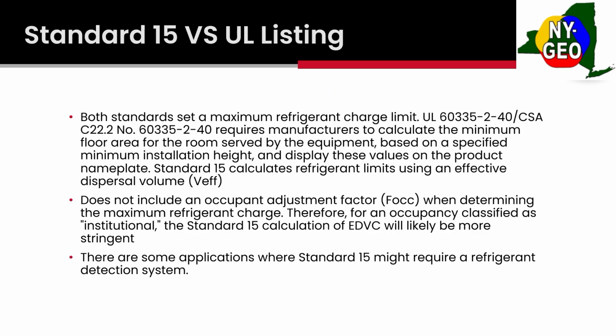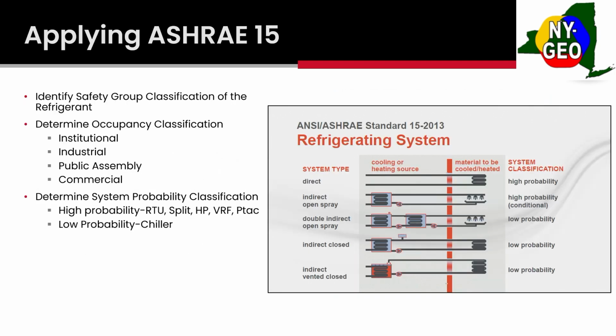So UL and Standard 15 are a little bit different. A lot of the manufacturers are going to use UL listing for their equipment, but when we design, we're going to be using ASHRAE 15. The difference is that UL prescribes several methods for the manufacturer to measure and calculate the releasable charge. This may result in a higher or lower releasable charge than in ASHRAE 15. ASHRAE 15, as we talked about before, has these different classifications that you're going to use to factor in your releasable charge. In an institutional place, you have a lot lower releasable charge than a commercial space.